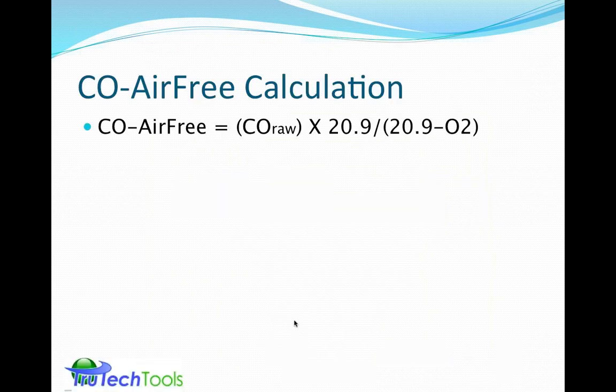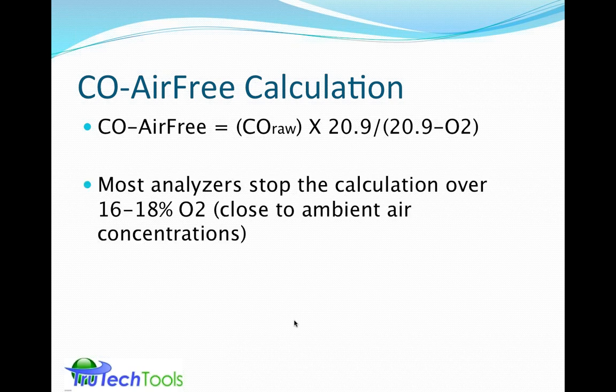The actual calculation for CO-AirFree is you take the raw CO number off the sensor and multiply by 20.9, and divide by the quantity of 20.9 minus the actual raw oxygen sensor number, the amount of oxygen coming off the sensor. Now, most analyzers stop the calculation over 16 to 18%, or conversely, don't start the calculation until they're below 16 to 18%, because those numbers are close to ambient conditions of 20.9. So your analyzer is not broken if you have really high oxygen levels. It just isn't going to calculate a CO-AirFree reading.